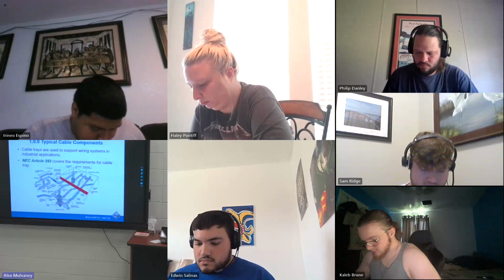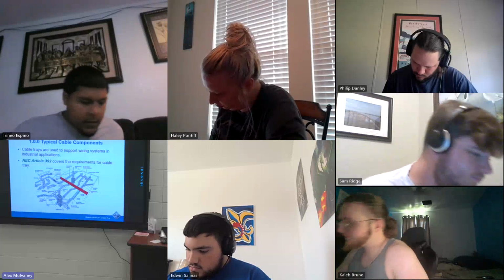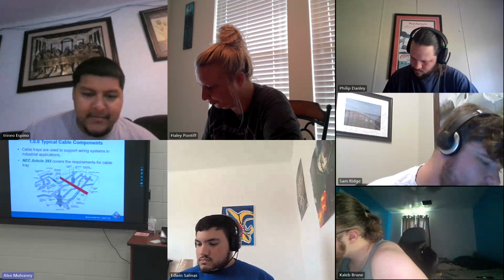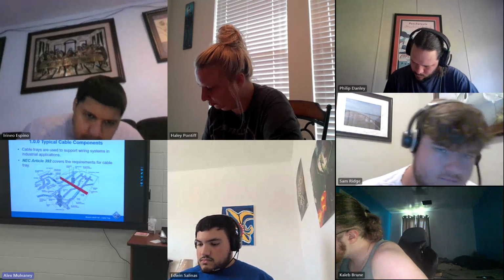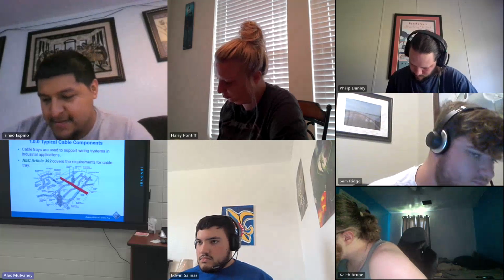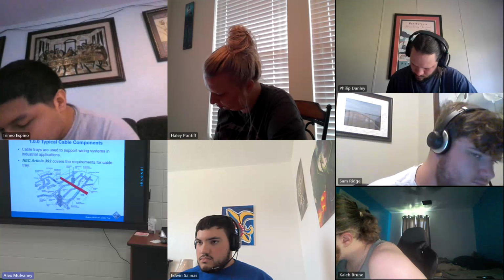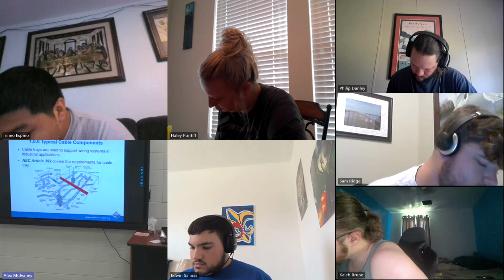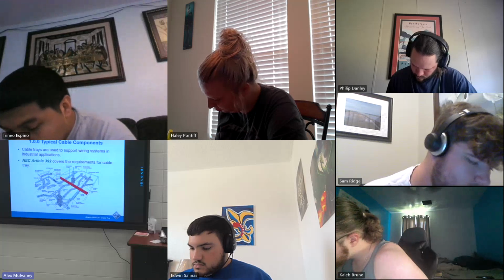trade terms. My first highlight is the second sentence on the page. NEC Article 392 covers cable tray installations along with the types of conductors to be used in various systems. Article 392, you'll be looking that one up a lot, probably next time you're here, but that's an important one. Third paragraph, third sentence is highlighted. Non-metallic trays are also available. This type of tray is ideally suited for corrosive areas and areas requiring voltage isolation.